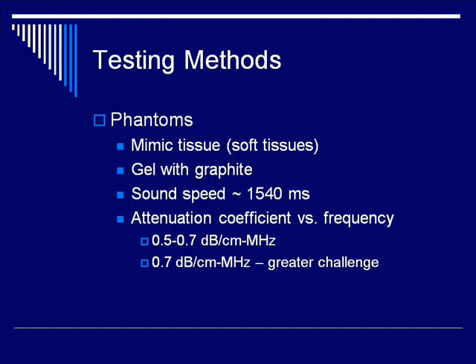The practical upshot is that within the gel, the speed of sound is 1540 meters per second, which is the same as it is in tissue on average, and the same speed that the machine assumes when doing calculations. As for the attenuation coefficient, it's generally between 0.5 and 0.7 decibels per centimeter per megahertz, which is similar to tissue. If you are choosing or buying these phantoms for your own practice, I would recommend the 0.7 decibels per centimeter per megahertz phantoms, as it will be more of a challenge to measure against for your quality assurance program.